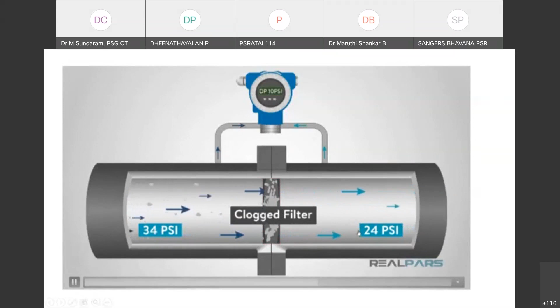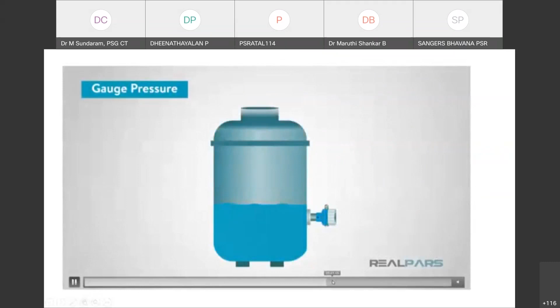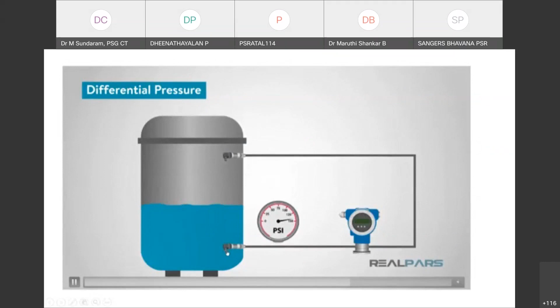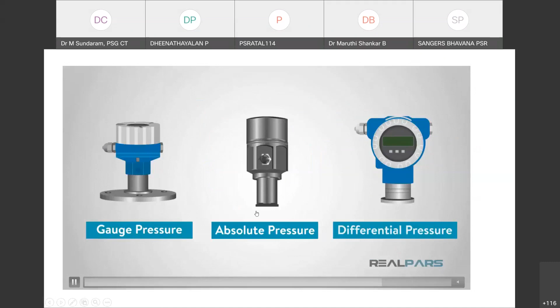When it is completely choked, you can notice this side is 34 and this side is 24. It indicates a clogged filter, which can be easily determined by this type. People will also use differential pressure in tanks. It is light air and dense water, so it has two different things. When the water fills up here, this pressure will increase. So you can determine whether the tank is full or empty using this also. So this is about three kinds of pressure, right? Pressure, flow, everything operates on this principle.